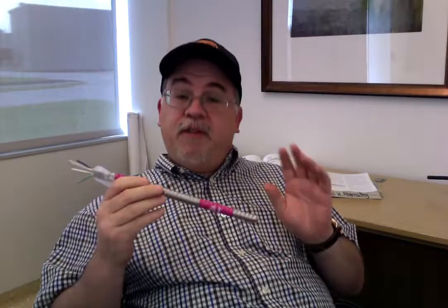This is called, officially from UL, an MC-PCS, or basically, we call it MC-LED. It's a product that's designed to allow Class 2 or 3 circuits or cable in the same cable assembly as your normal power conductors. And you don't need a separation.